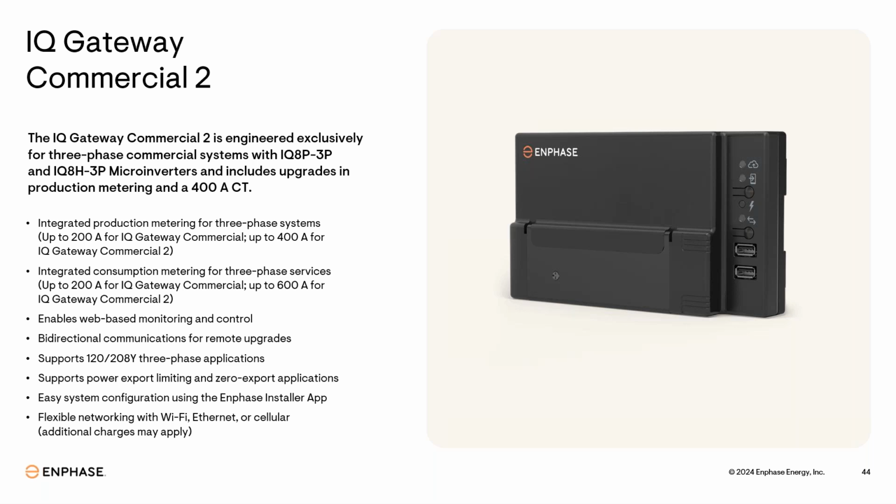If you do have projects that are larger than 150 kW or more than 276 micros, all that means is that you need an additional gateway with line filter. So you're going to build these things modularly out at 150 kW approximate increments. Again, projects that are over 150 kW or 276 microinverters require an additional gateway.